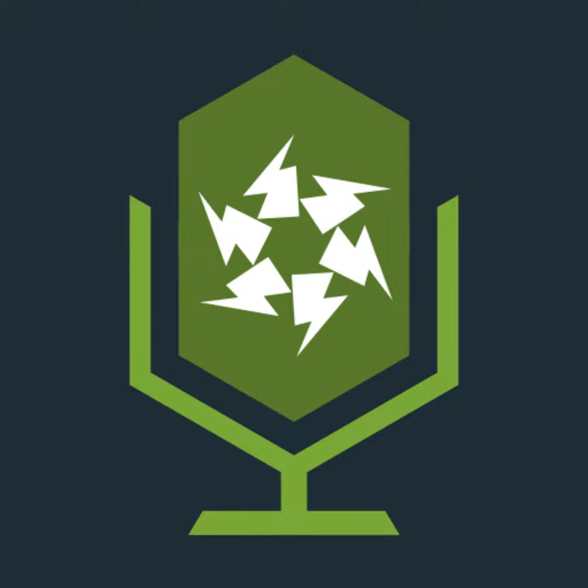And if I was to say to myself, right, I'm going to use a semiconductor, can I use a semiconductor for isolation? So I'm going to go down the device lists till I find semiconductors, and I find them there, third from the bottom on that page, device with semiconductors, and it actually says no across the board for isolation and emergency switching.